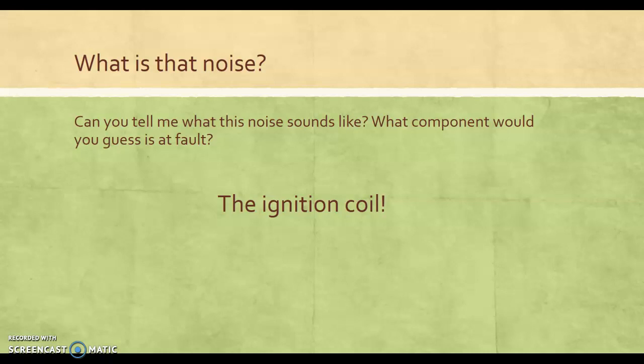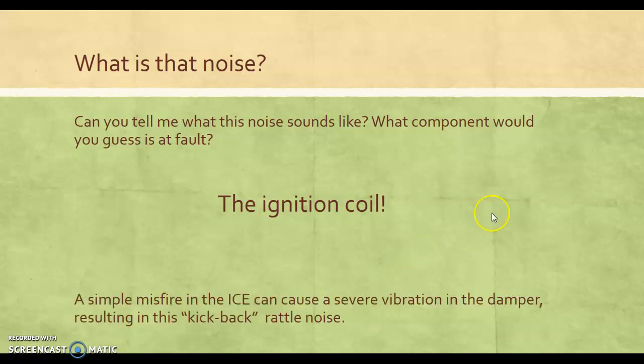So when it hammers back in, it hits the electric motor, magnetic field, rotor, stator combo, and it doesn't like that. The damper is there to smooth that out, but it can't handle that much. So the springs collapse, and then you get that banging, rattling noise that is pretty gnarly. So that is that. Pretty crazy.